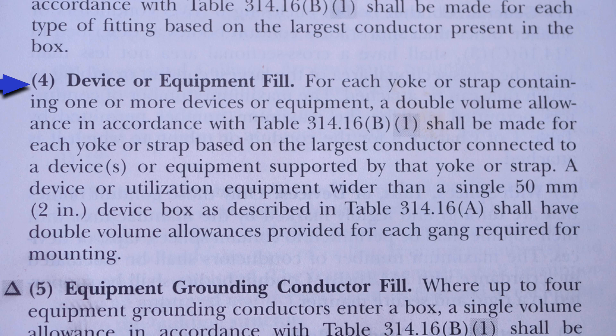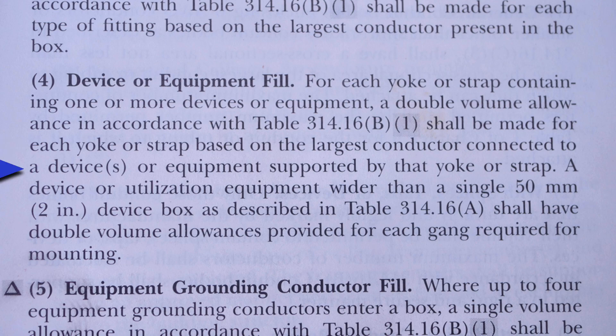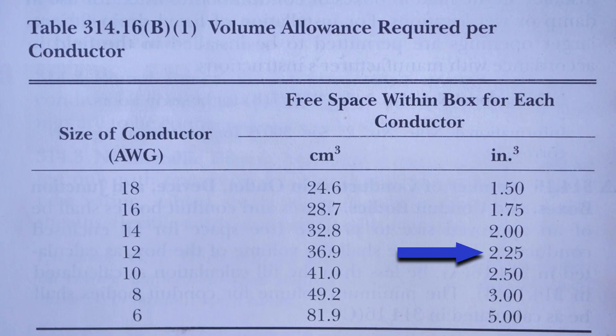Here we are at NEC 314.16B4, device or equipment fill. For each yoke or strap containing one or more devices or equipment, a double volume allowance in accordance with table 314.16B1 shall be made for each yoke or strap based on the largest conductor connected to a device or equipment supported by that yoke or strap. So our switch will get a double volume allowance and our receptacle will get a double volume allowance. Our largest conductors are 12 gauge, so it's 2.25, and we have two volume allowances for the switch and two for the receptacle — 2.25 times 4 equals 9 cubic inches.